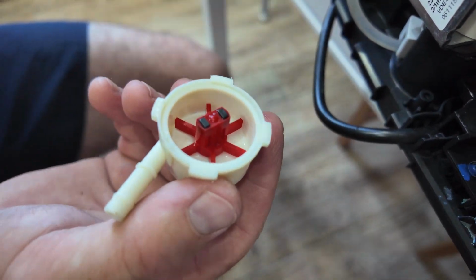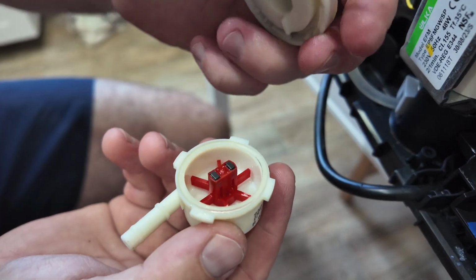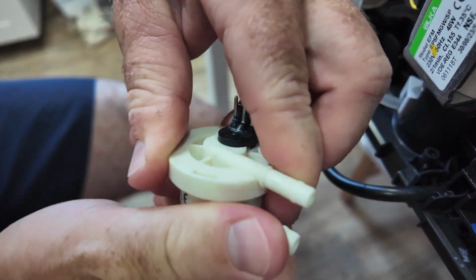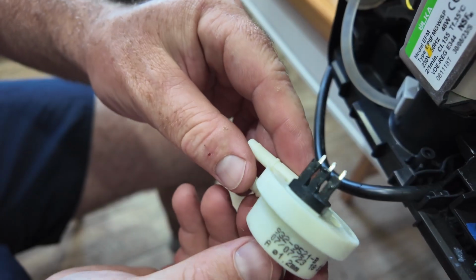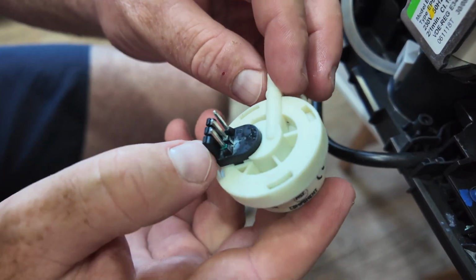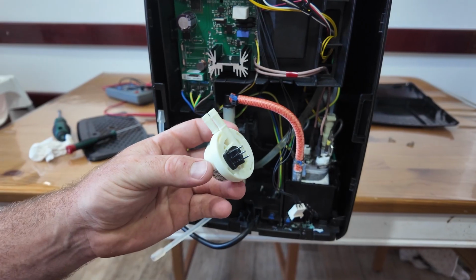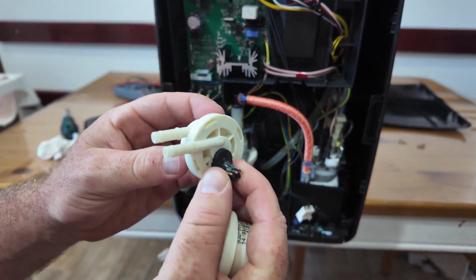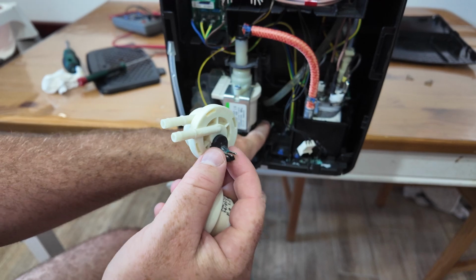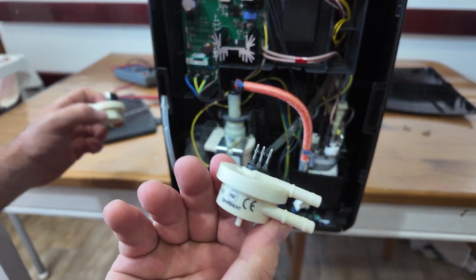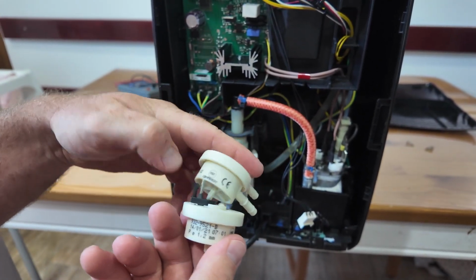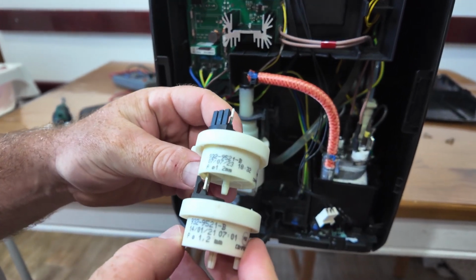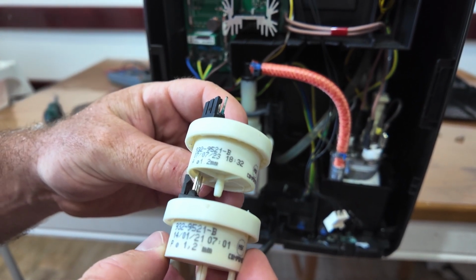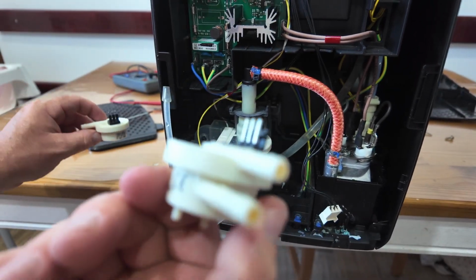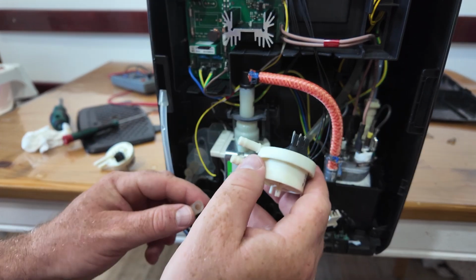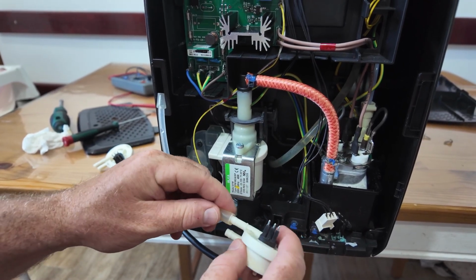So this had a rubber ring to seal the water, and I have another one, a used part, just to check it. This is my part number, and probably we have to replace this one. So this is the broken one that we have unmounted from there, and I have broken a leg. I don't know if you see that. And this is also a used one. They're technically the same component. Let's see. The codes are the same, the year is different. So this should be working because this is from a working machine. So I won't put it in place. This is just for test purposes.